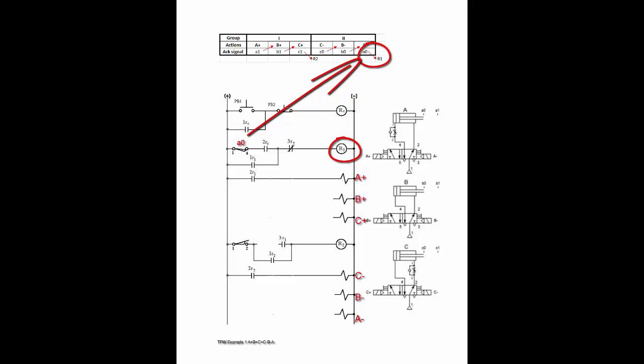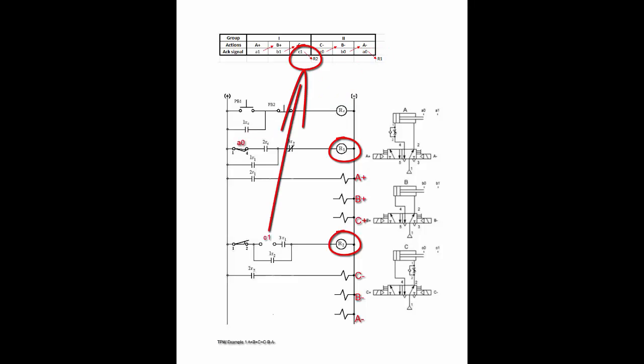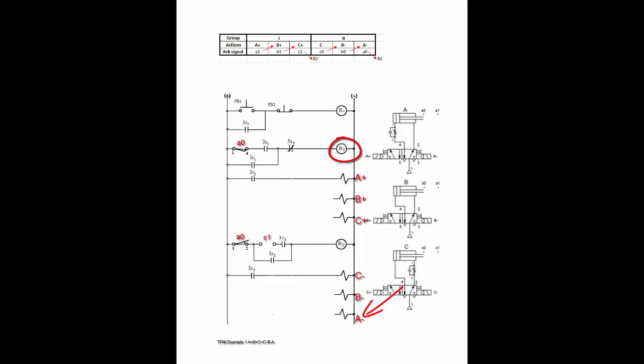From the table above, R1 is turned on by A0. R2 is turned on by C1. When R2 turns on, R1 is turned off by contact 3R2, which is included in the template. When R1 is turned on again in the next cycle by A0, R2 is turned off by the special normally-closed-but-held-open limit switch contact A0 (1-2 pair), which is activated by the last action of the given sequence — A minus in this example.